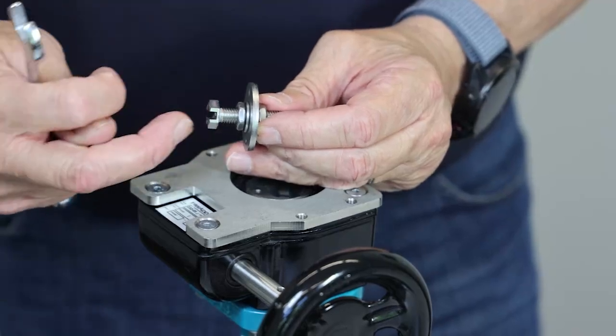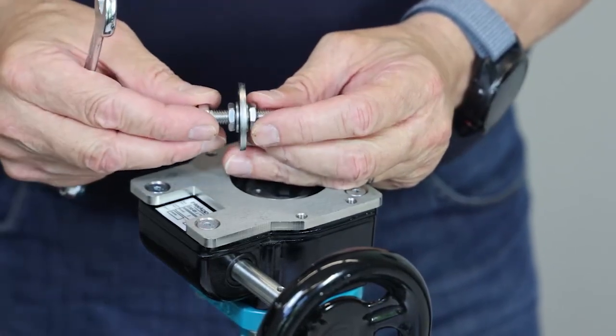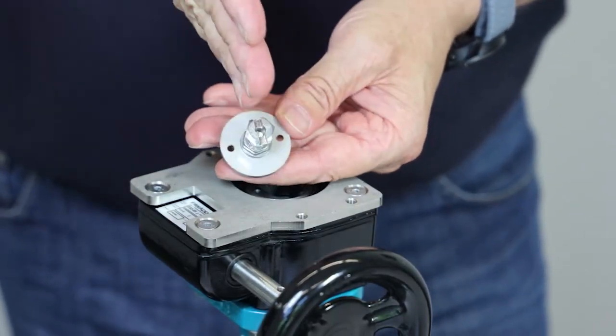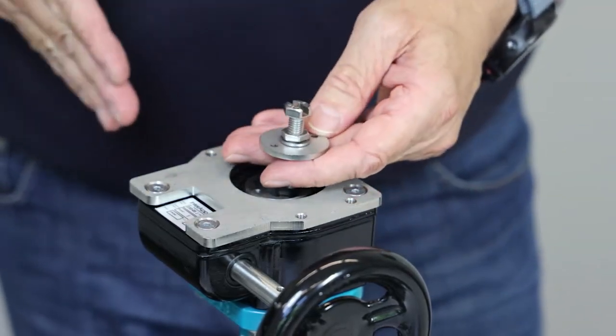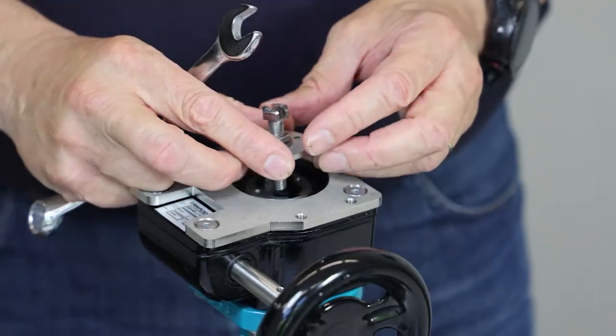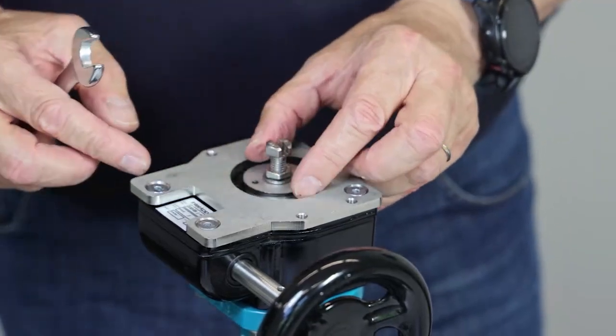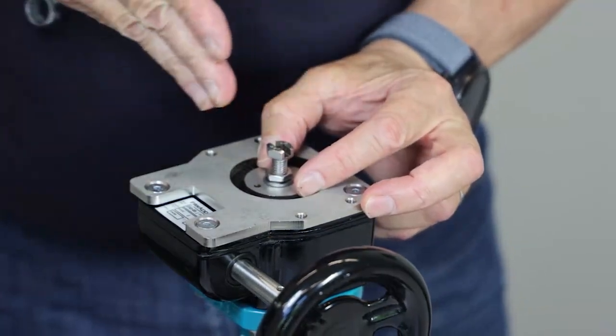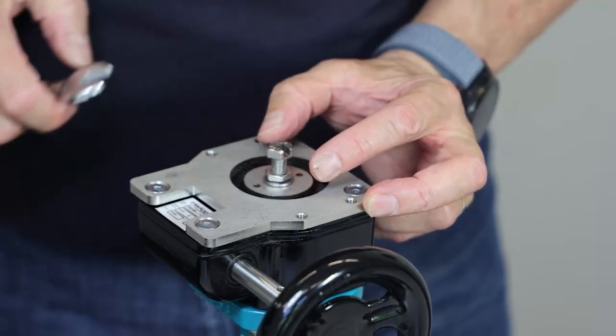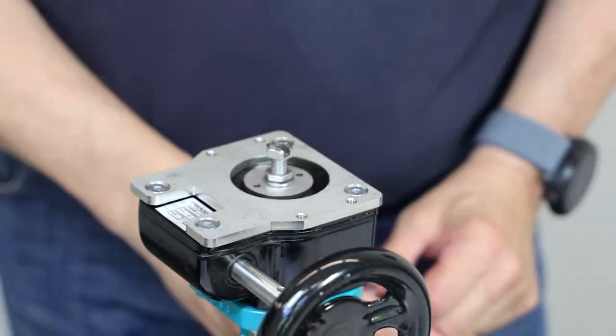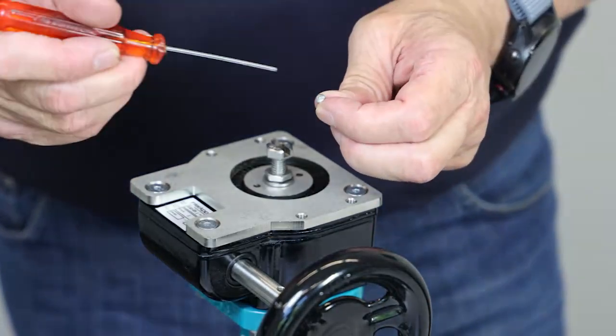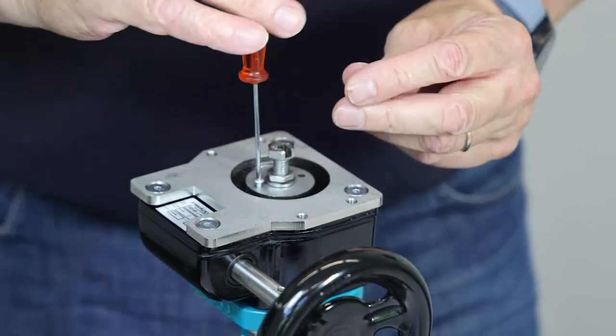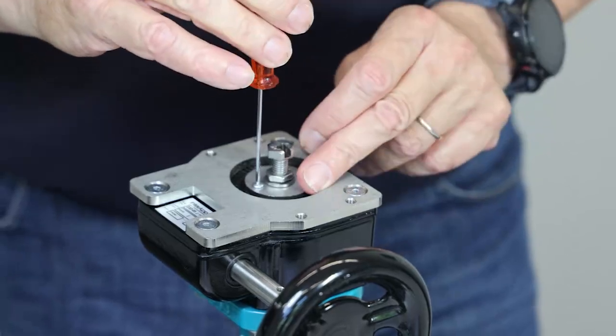Besides the height of 22 to 23 mm, it is as well important now to adjust the screw properly that the slot in the screw will correspond to the position of the disc and finally to the driver on the limit switch box. Once the nuts are properly tightened on both sides, check if the slot is now in the right position. When done, you can use the small screws that you removed before and screw in the driving plate on the gearbox.